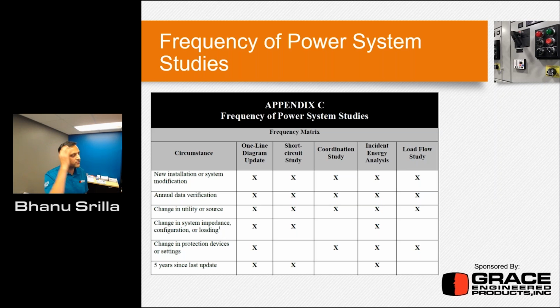When you try to do the power system studies, these are the things that you need to do. Five years since last update, this is what I was talking about, incident energy analysis has to be performed. And there are a lot of changes that have been brought into place with the IEEE 1584 standard in 2018. Just make sure that you verify your incident energy or arc flash calculations to the latest edition of 1584, and make sure you make those adjustments as required, okay?